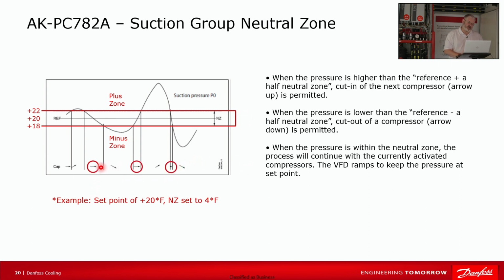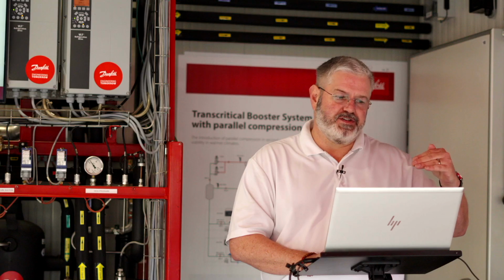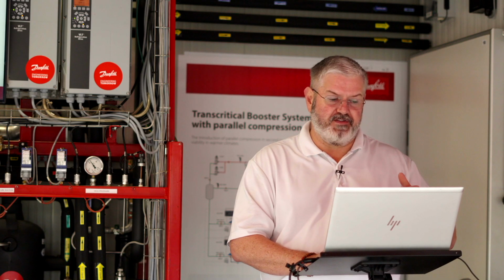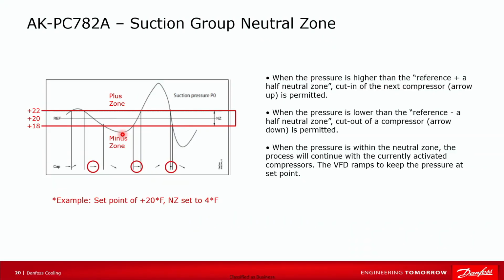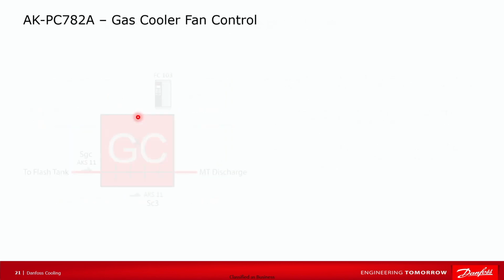And then there's a little highlight to show that here we're just moving, no call for going up or staging down. If you go to one of our controllers and you see plus zone or minus zone, that confuses some people, but plus means I've either just added or I'm about to add capacity, and it means I'm still above set point +2, or I'm still below set point -2 if you see minus zone. That'll display until you get back up into the neutral zone, at which point it'll just say normal control. So that's our suction group control.